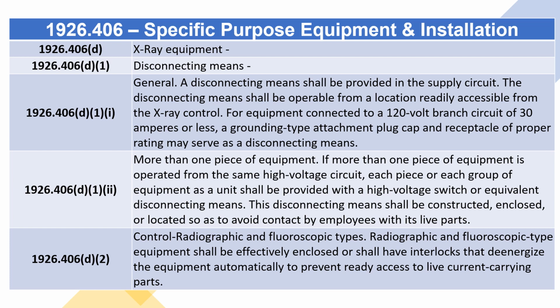1926.406(d)(1)(ii) More than one piece of equipment. If more than one piece of equipment is operated from the same high-voltage circuit, each piece or each group of equipment as a unit shall be provided with a high-voltage switch, or equivalent disconnecting means. This disconnecting means shall be constructed, enclosed, or located so as to avoid contact by employees with its live parts. 1926.406(d)(2) Control. Radiographic and fluoroscopic types. Radiographic and fluoroscopic type equipment shall be effectively enclosed or shall have interlocks that de-energize the equipment automatically to prevent ready access to live current carrying parts.